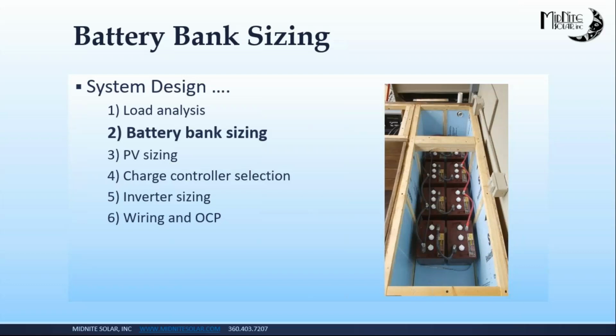Just right is 14.8 volts as per the battery manufacturer specifications, plus temperature compensation. Temperature compensation is very important. That's a function of, if the batteries are cold, you have to elevate the voltage.